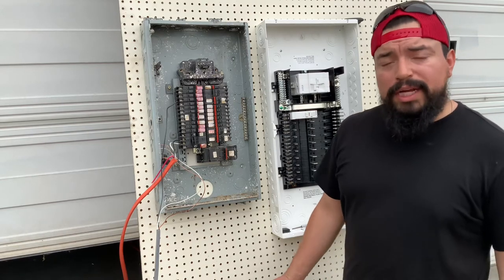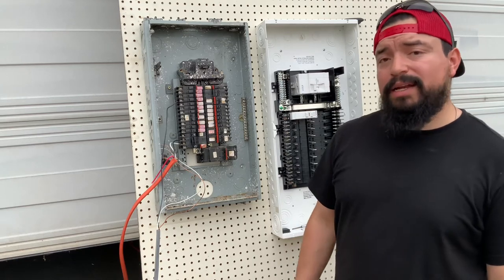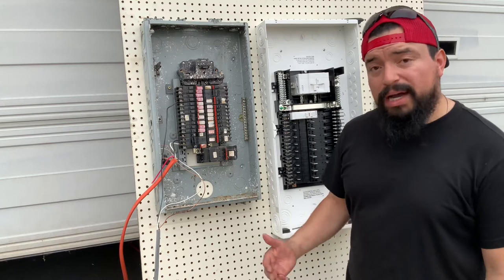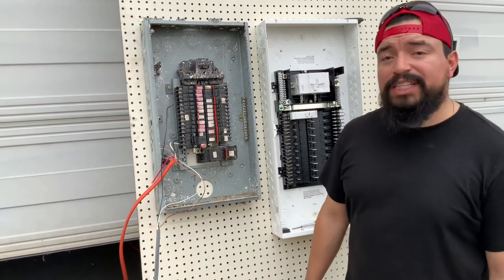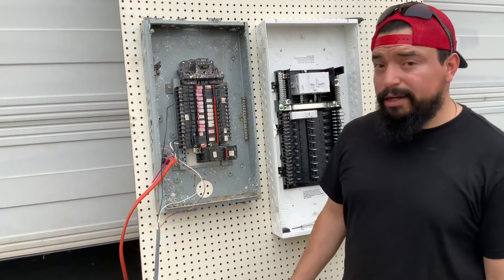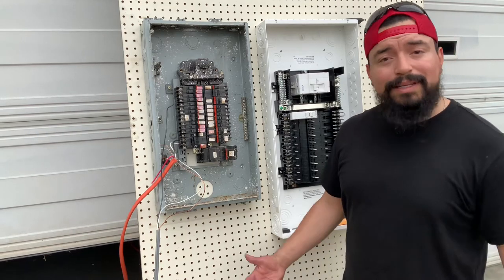So that's what we're doing today — we're raising awareness that if you have one of these panels in your home or in your business, is it worth keeping it? By the way, this panel never had any issues, and that's what I keep hearing over and over. But whenever that issue arises in your home, there's a 50-50 chance that it's going to trip or that it won't trip. And if it doesn't trip, as you can see, it causes arcing — and arcing causes fires. So is it worth keeping in your home?